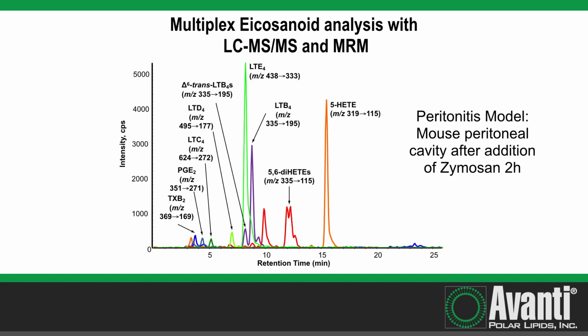So here's an example now of multiplexing this, because typically these mass spectrometers, as I had previously mentioned, work in the millisecond time frame. So you can run through ion transitions or ion chemistry quickly within 5 to 10 milliseconds. Maybe you want to go a little bit longer, 200 milliseconds, doesn't really matter. Here's the PGE2 example. The machine was running 351 to 271 to detect PGE2. It does this in a cyclic process. And so the only place where PGE2 came off was this chromatographic peak.